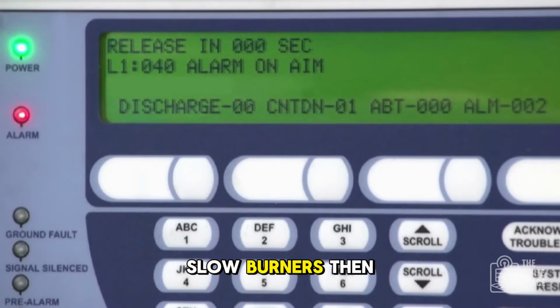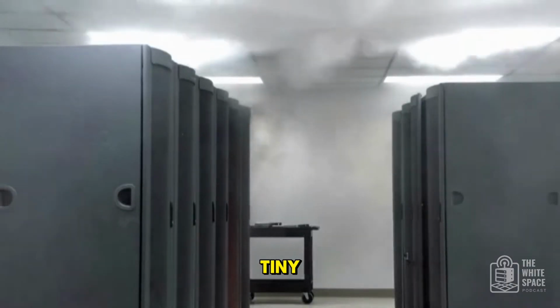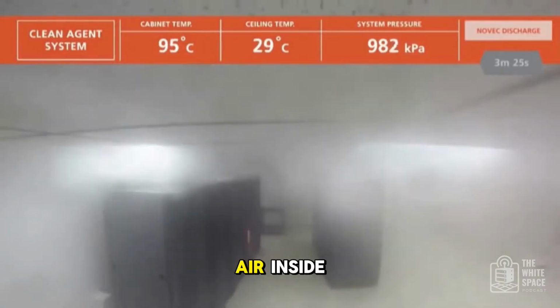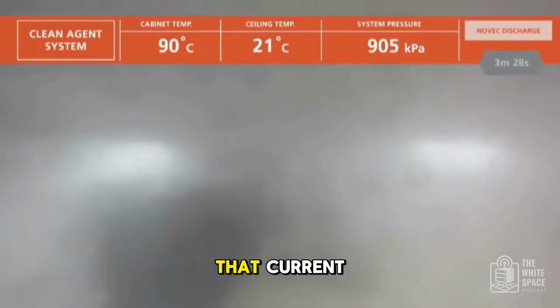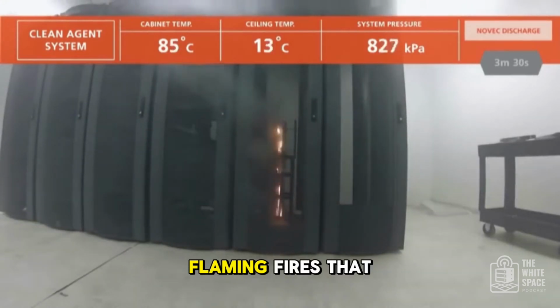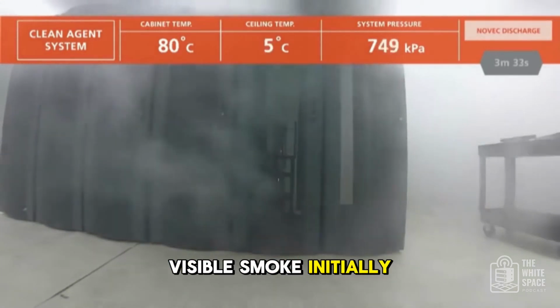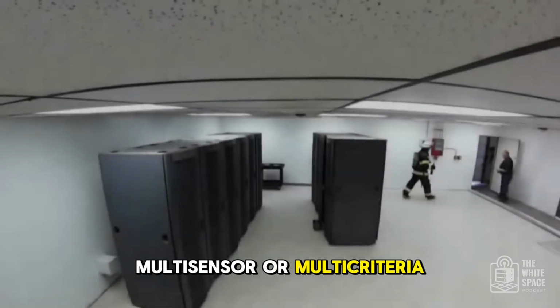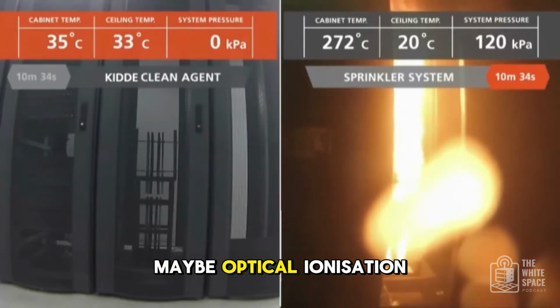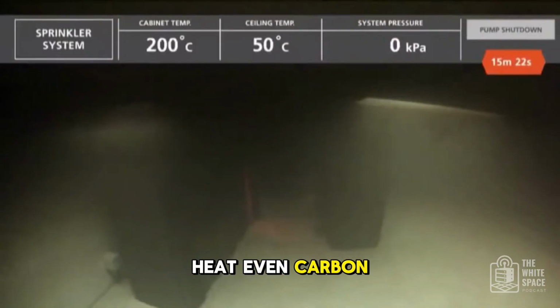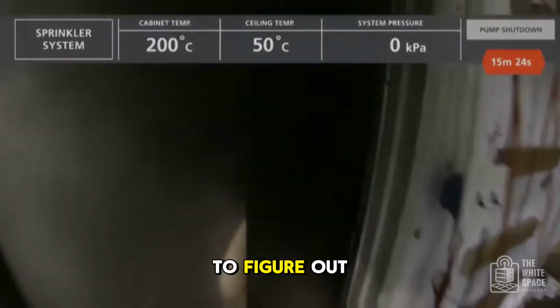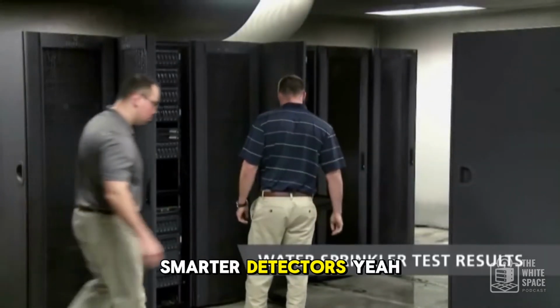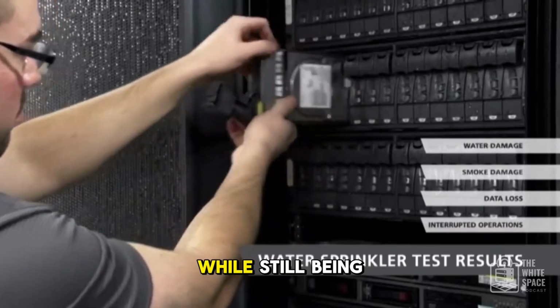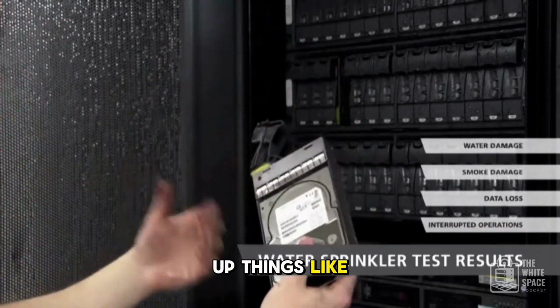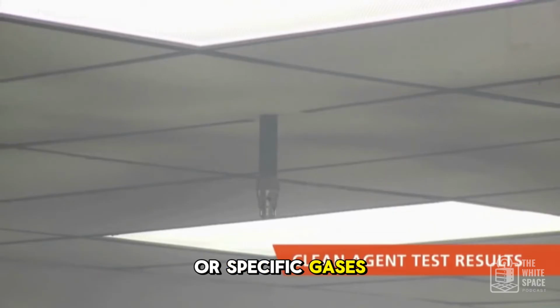Right, slow burners. Then you have ionization detectors. They use a tiny radioactive source to create an electrical current in the air inside. Smoke particles disrupt that current. They tend to be better for faster flaming fires that might produce less visible smoke initially. Okay, photoelectric and ionization. Got it. And now, many are multi-sensor or multi-criteria. They combine different sensors, maybe optical, ionization, heat, even carbon monoxide, and use algorithms to figure out if it's really a fire. Smarter detectors. Yeah, much better at avoiding false alarms while still being sensitive. They can pick up things like rapid temperature rises or specific gases before you even see smoke.